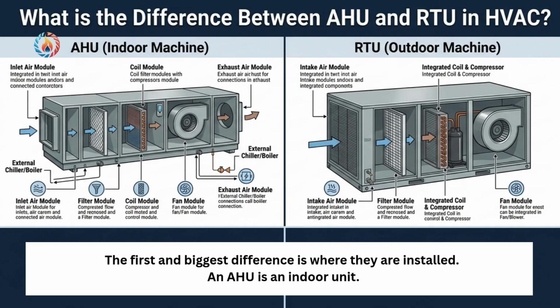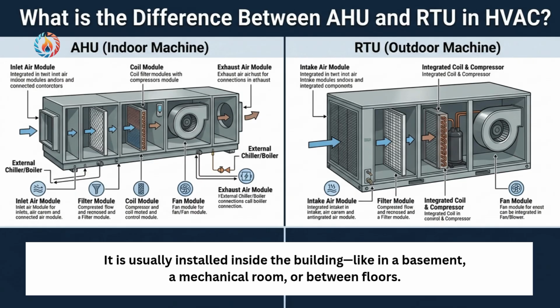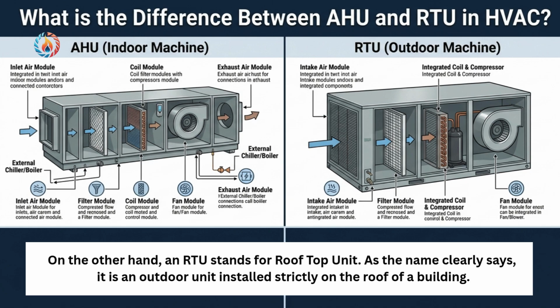Location: the first and biggest difference is where they are installed. An AHU is an indoor unit. It is usually installed inside the building, like in a basement, a mechanical room, or between floors. On the other hand, an RTU stands for rooftop unit. As the name clearly says, it is an outdoor unit installed strictly on the roof of a building.